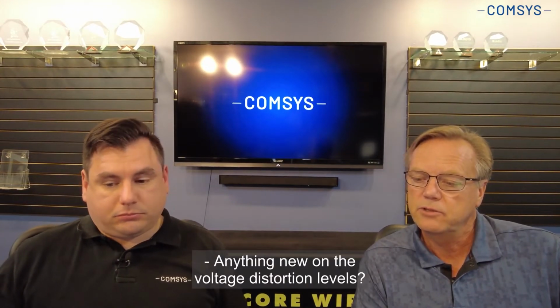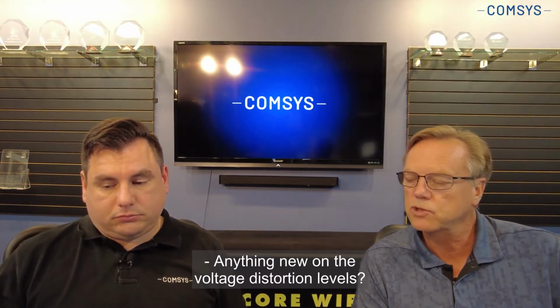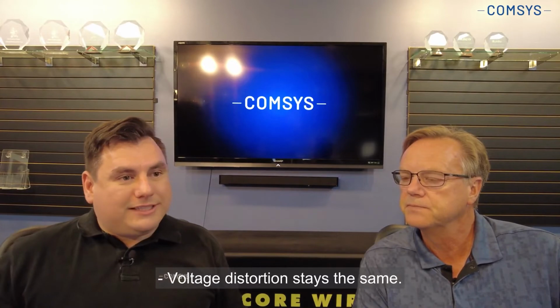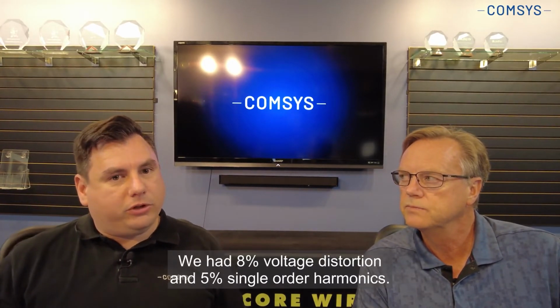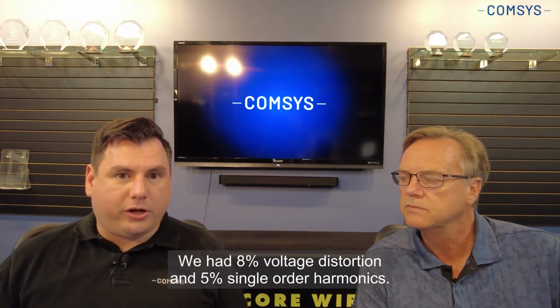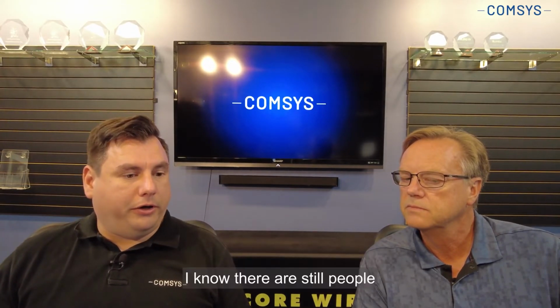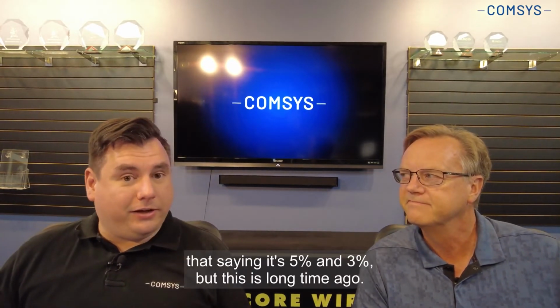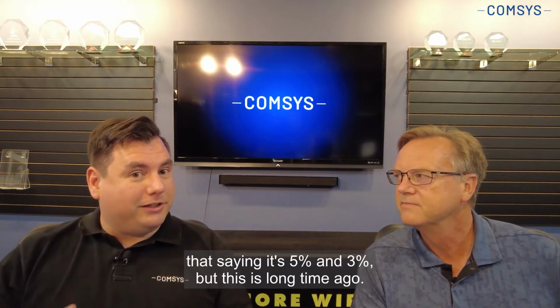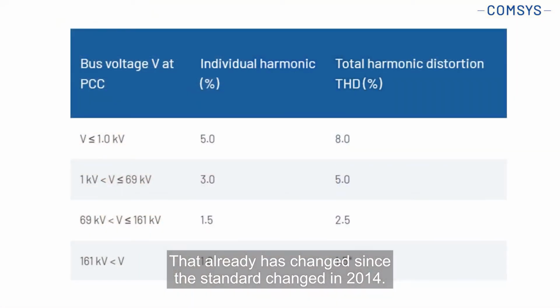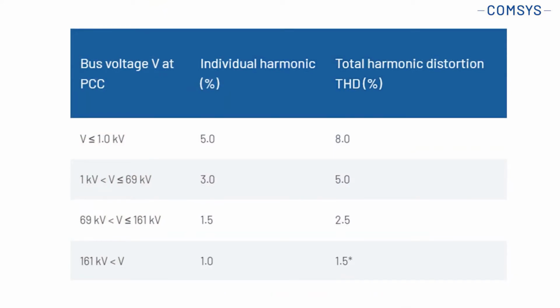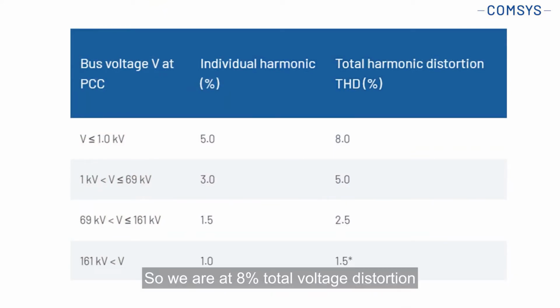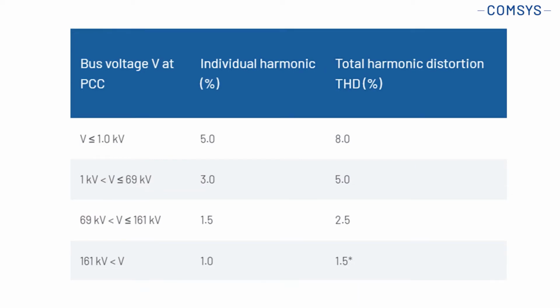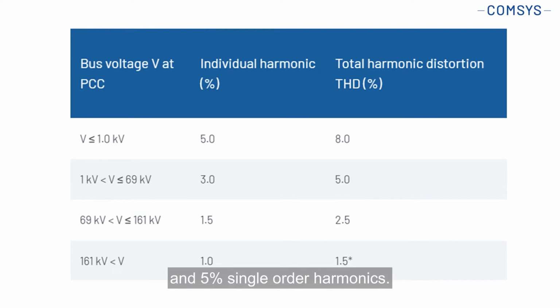Absolutely, yes. Anything new on the voltage distortion levels? Voltage distortion stays the same. We are at 8% voltage distortion and 5% single order harmonics. I know there are still people that say it's 5 and 3%, but that is a long time ago. That already changed when the standard changed in 2014. So we are at 8% total voltage distortion and 5% single order harmonics.